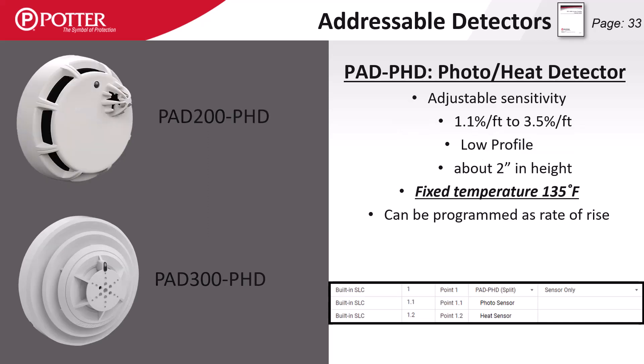The PAD-PHD is a combination photo heat detector. Potter's combination detectors include individually mappable elements, and through the programming software the device can be configured as a single detector or split. This allows the individual elements to have the same characteristics of their standalone counterparts while only consuming a single SLC address. Heat detectors that are part of a multi-element detector have a fixed temperature set point of 135 degrees and are not adjustable.